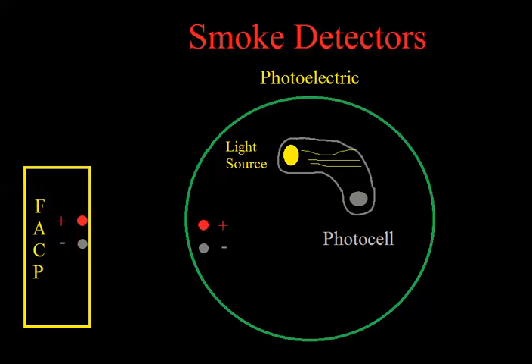The way they detect smoke is when smoke enters the chamber—I'm going to simulate smoke here, let's say this is smoke—the light refracts off the smoke particles. The light will go every direction, it'll scatter. But some of it will hit this photocell. When the photocell sees light, it produces a current.